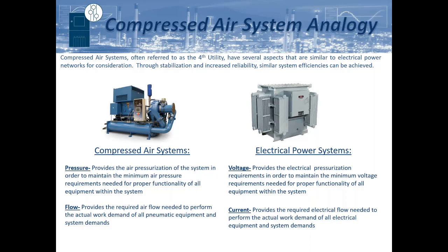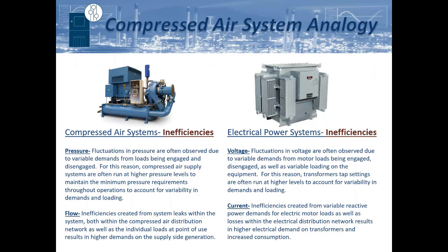And when you have inefficiencies within that flow, like in a compressed air system, if you have a large load coming in that requires a lot of flow to perform that function, it's going to drop the pressure throughout that network. The same holds true with electrical systems. When you have a large electrical motor that is starting, it requires a lot of reactive power, magnetizing current, to get that motor elevated and spinning appropriately. And all of the neighboring equipment are going to see those fluctuation changes as well, or see that pressure change or voltage drop.